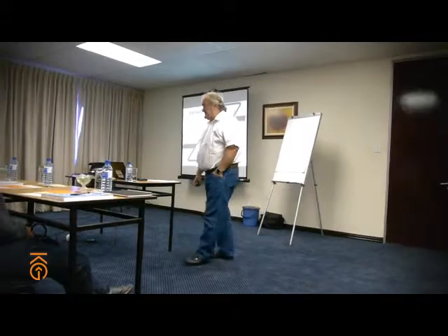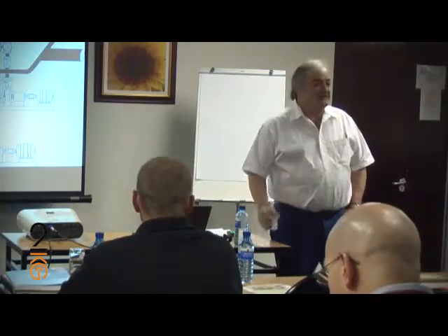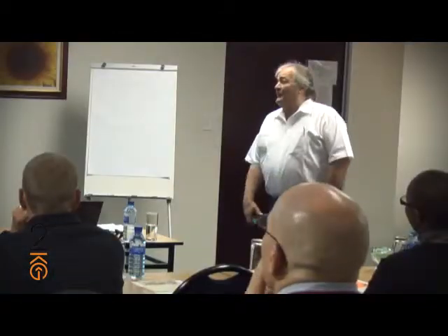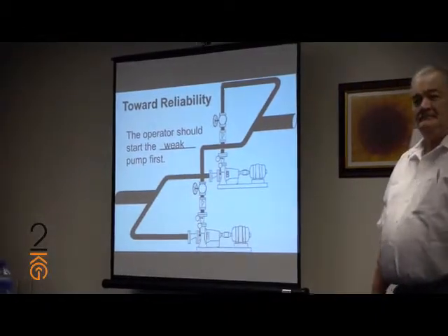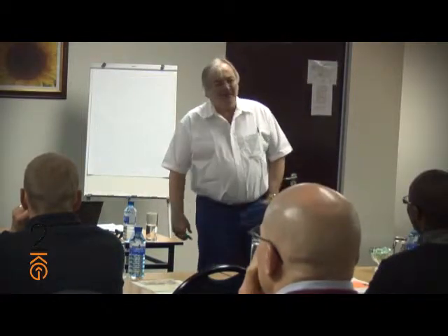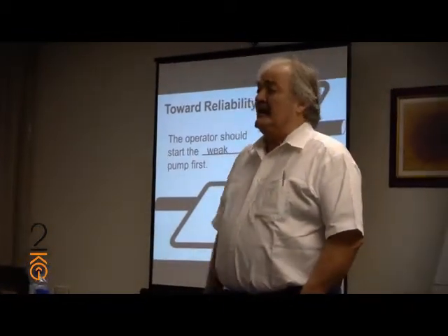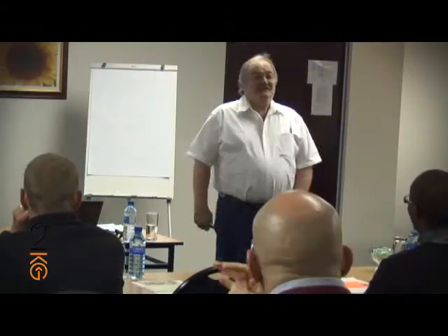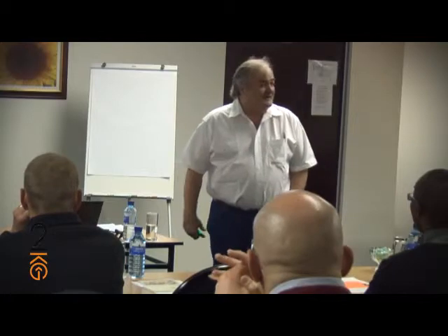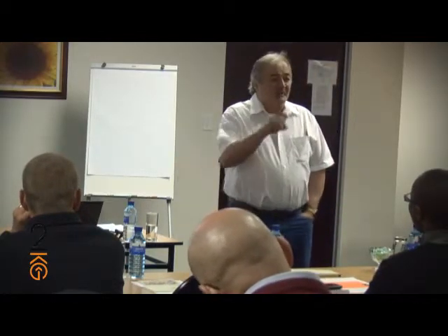So the process engineer says to the operator, I want you to start those two pumps. Which pump do you start first? The operator should start the weak pump first. Well, you say, wait a minute, those are identical pumps. They both have the same horsepower, the same kilowatt motor, the same pump, came down the assembly line together, the same impeller, the same shaft, same bearings. There's one number different in the serial number. They were bought together. One serial number ends in 6, the other serial number ends in 7. Other than that, they're identical pumps.